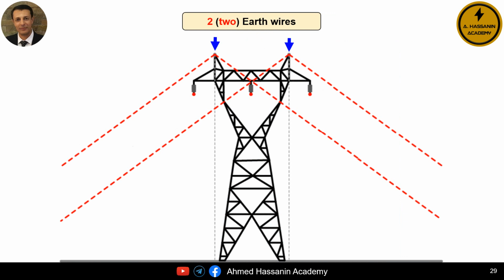Therefore, the only practical and feasible solution for towers operating at 500 kilovolts, for example, or for towers with large horizontal spacing or separation between phase conductors, is to use two shield wires or earth wires or ground wires, as clearly shown in the image in front of us. In this configuration, each shield wire or earth wire or ground wire is responsible for protecting a specific area, let's say half of the tower. For instance, the first shield wire protects the insulators of phase conductors R and S, while the second shield wire protects the insulators of phase conductors S and T. This solution is much more economically efficient and practical compared to using a single shield wire at a very high elevation.